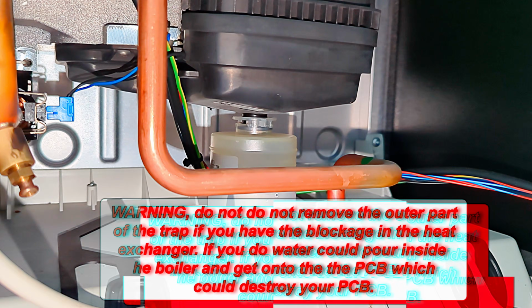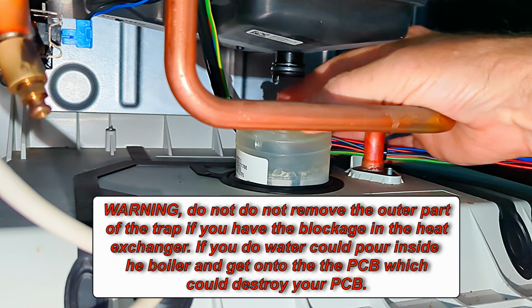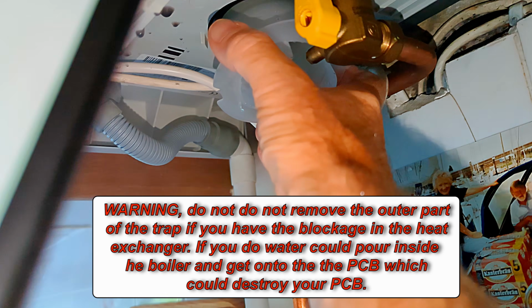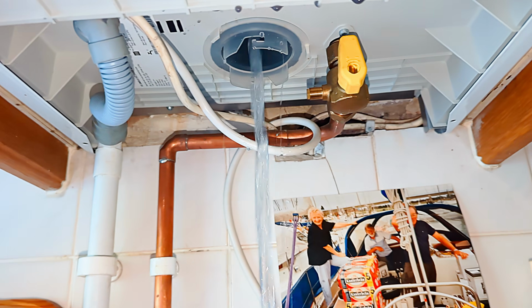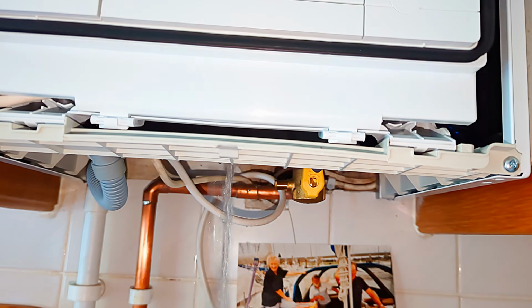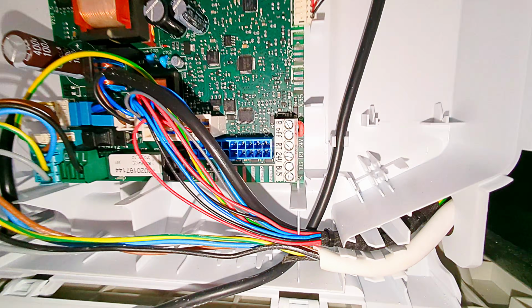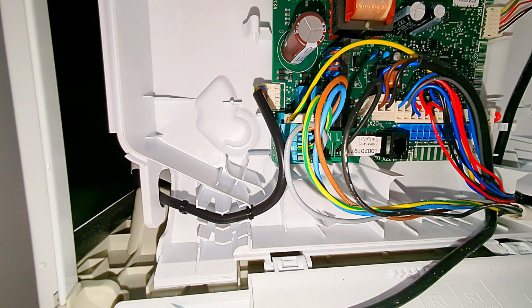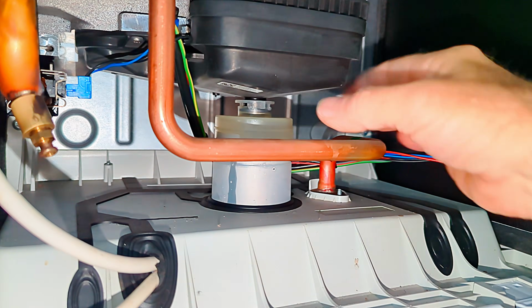Word of warning here. If you have a blockage, then don't take that outer part of the trap off, because when you poke something up inside it, all that water is going to pour out inside your boiler. And then there's a possibility it might run down onto the printed circuit board, which is really expensive, and destroy it. I'm just showing you it this way for demonstration purposes. So don't remove the outer part of the trap like I am here. Leave it in position.